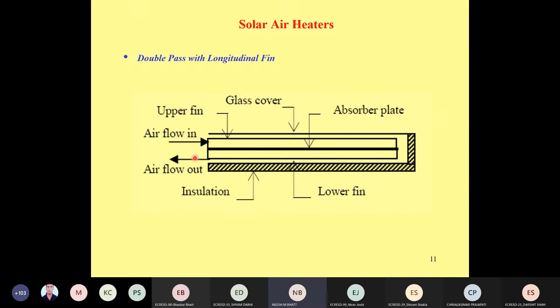So now, for the same area and same temperatures, if we go for the staggered fin, for the same convective transfer coefficient and same delta T, if you go for a fin, that is an extended surface, then of course the heat transfer area increases, and so the heat transfer increases and we can get a little higher air outlet temperature. So the first modification that people have done is the staggered fin. Then another option is that rather than staggered fin, one can go for longitudinal fin also. So the longitudinal fins are provided over here.